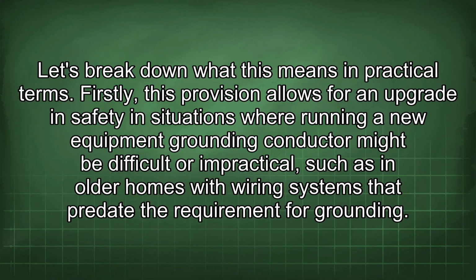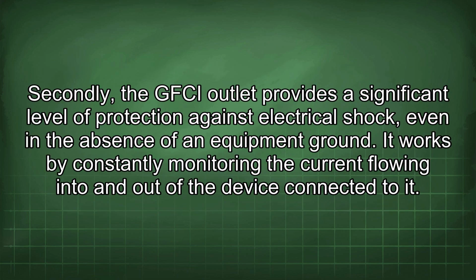Let's break down what this means in practical terms. Firstly, this provision allows for an upgrade in safety in situations where running a new equipment grounding conductor might be difficult or impractical, such as in older homes with wiring systems that predate the requirement for grounding.